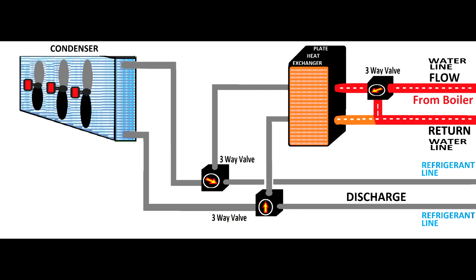I came across a situation where I had a leak inside the plate heat exchanger, and the refrigerant pushed against the water. Can you imagine? The refrigerant is at about 10 bar or 7 bar, depending on how warm or cold it is outside, but the water has only 2.5 bar. So the refrigerant will push into the water, and that's bad. That's why the main quantity of heat will be recirculated. You see the three-way valve will push more, and it will bypass the plate heat exchanger.